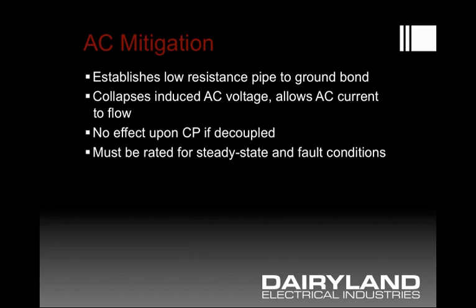AC mitigation is accomplished by establishing a low-resistance connection between the pipe and a grounding system, which collapses the induced AC with AC current flowing as a result. One could measure and find that the induced AC voltage is now very low. Using decoupler products — DC blocking devices that simultaneously mitigate AC — there will be no effect upon the cathodic protection. Such a system must be rated for both steady-state and fault conditions.